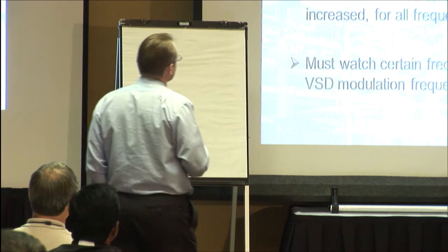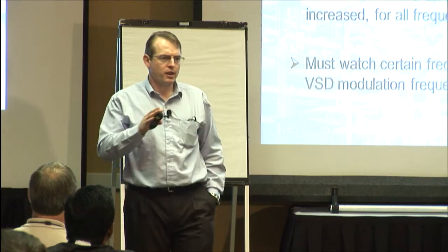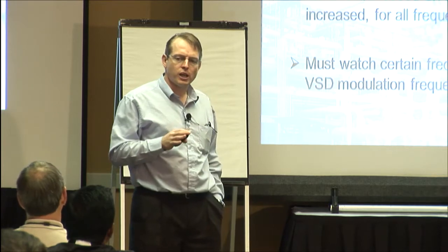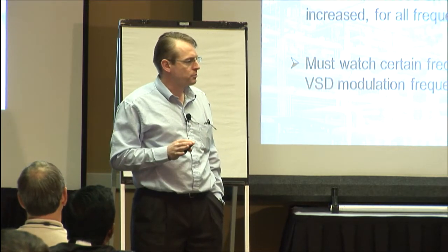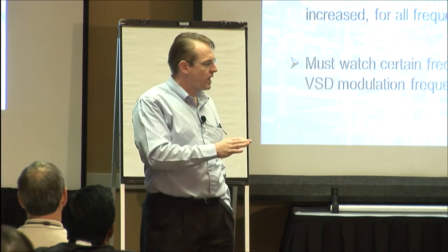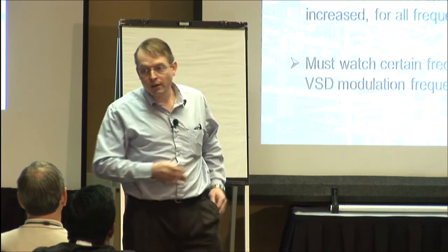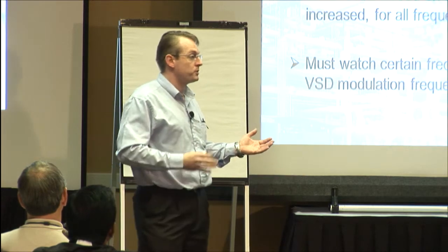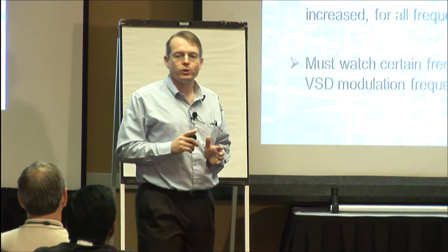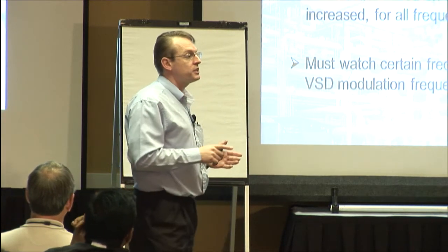Before we do that, just as a quick reminder, I haven't thrown these graphs in because I didn't want to waste too much time on this today. If anyone wants them, we can go and dig them up. But remember that you get some very interesting effects as you change your test frequency on the UltraProbe. With your VSD, remembering someone mentioned the other day about the modulation frequency of the VSD or VFD, it can vary anywhere from, say, 4 kilohertz up to perhaps 16 kilohertz. What happens, of course, is the harmonic of that sampling frequency or modulation frequency can interact.